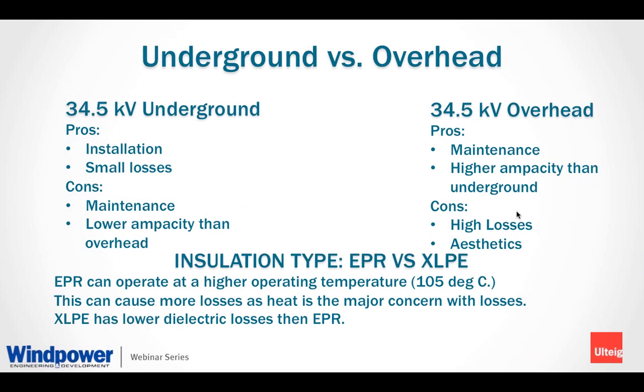Change the next slide here, and the underground installation can improve aesthetics versus your overhead because it's buried in the ground. Underground cables typically will have less losses than overhead conductors, but they cannot carry as much power from the heating effects I had explained earlier. If properly installed, the weather and storms and ice and snow and sleet don't affect the underground quite as much as the overhead conductors.